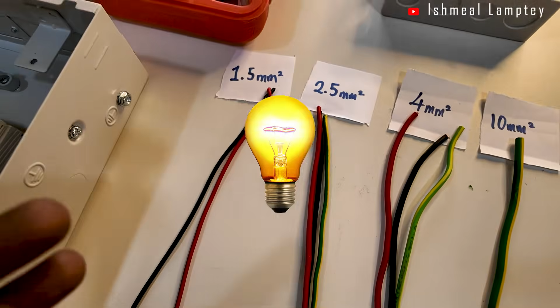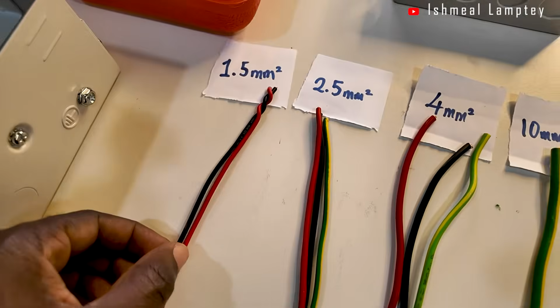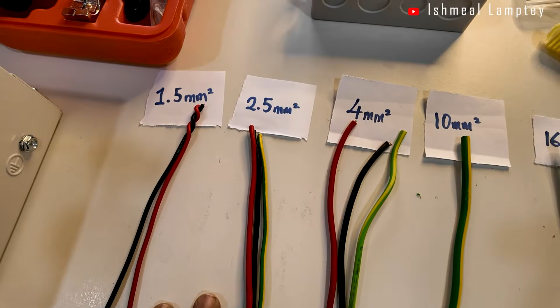So you have your lights and fans, then you're looking for this size of cable because the power they carry is a bit small, and they're able to cater for those appliances or equipment. Then you have a 2.5 mm cable, usually for your socket system — sockets for TVs, fans, fridges, among others. 2.5 mm is basically used for that kind of work, so you're able to have the correct size of power going through these cables.